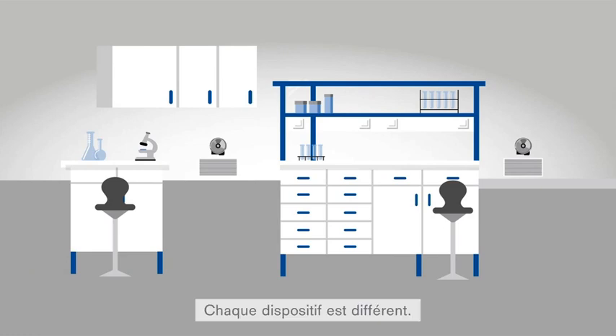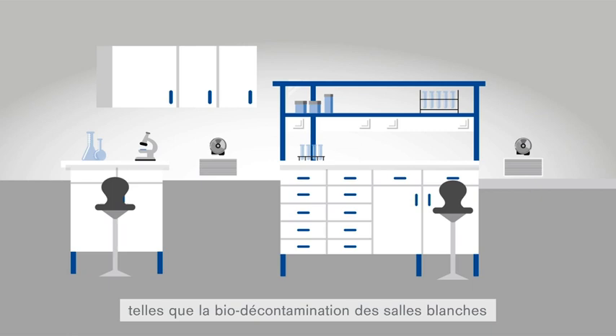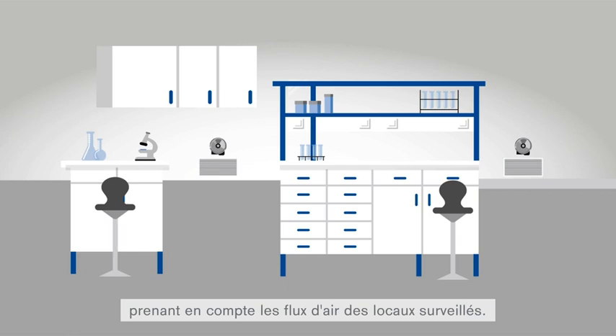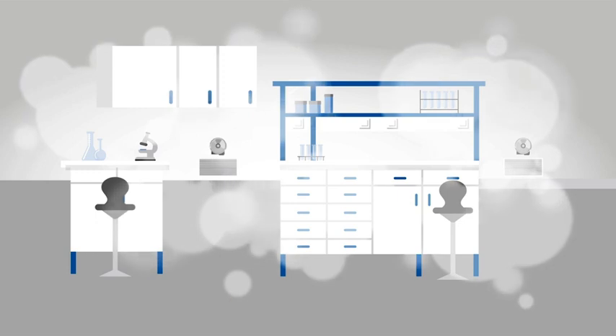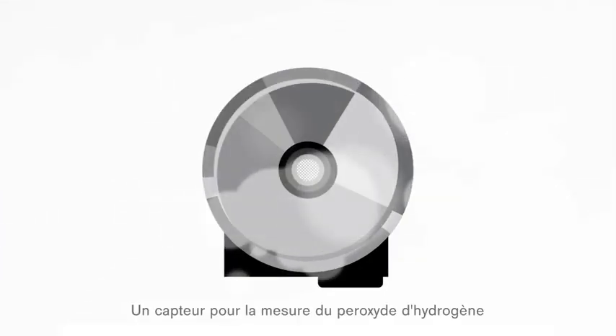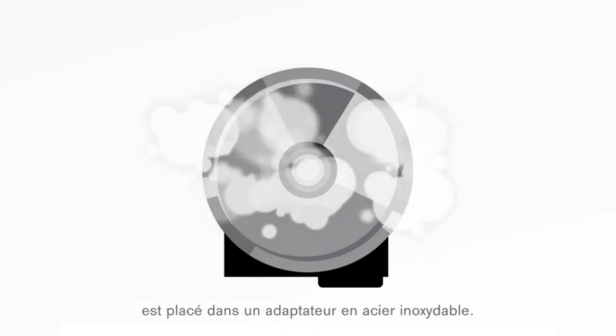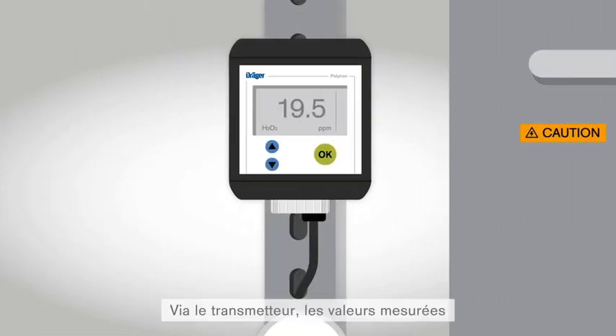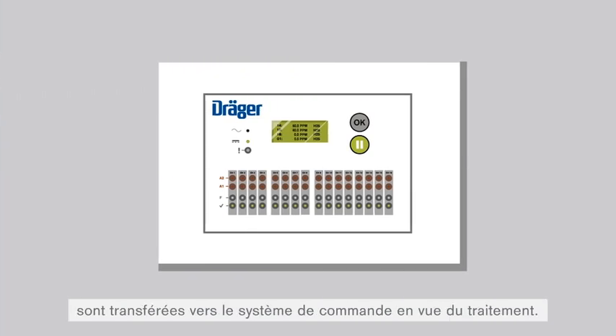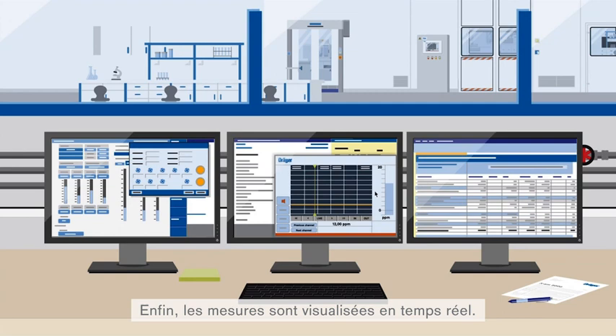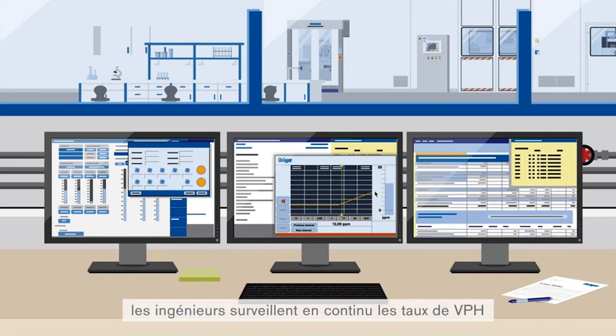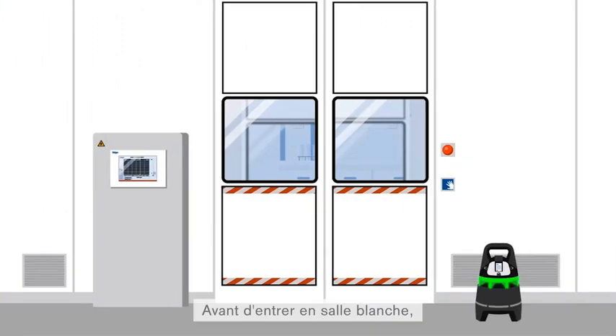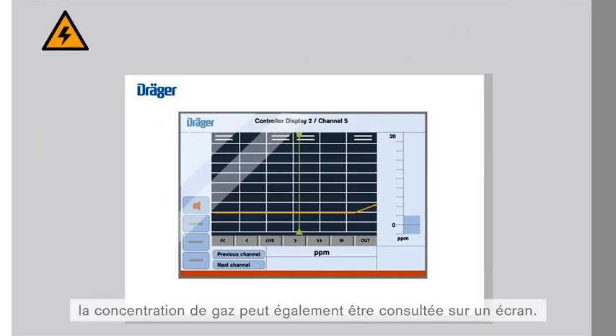Each deployment scenario is different, but there are established solutions. One example is the bio-decontamination of clean rooms by installing a stationary gas detection system that takes local air currents into account, eliminating contaminants throughout the entire clean room. A sensor for measuring hydrogen peroxide is installed in a stainless steel adapter, ensuring a defined measurement environment. The measured values, via a transmitter, are transferred to a controller for processing. Finally, the measurements are visualized — in the technical control room, engineers can always view the hydrogen peroxide concentration and respond to an alarm immediately. Right before entering the clean room, the gas concentration can also be viewed on a monitor.